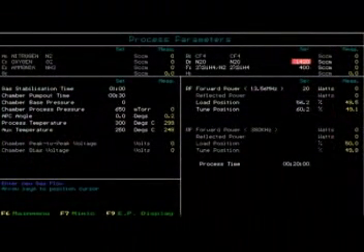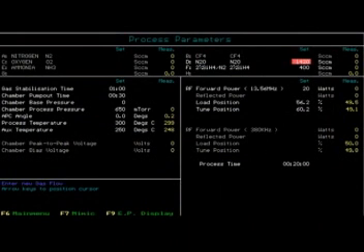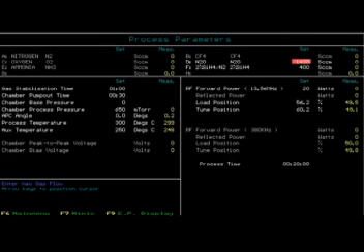There are two numbers that should be monitored during deposition: the reflected power and chamber bias voltage. The tuning network will automatically adjust the load and capacitor positions to reduce any reflected power — this number should be close to zero. Chamber bias voltage affects film quality as well as the deposition rate and should remain near constant with the same recipe throughout the process. If the number varies, this indicates a change in the chamber condition, and the MRC staff should be notified.